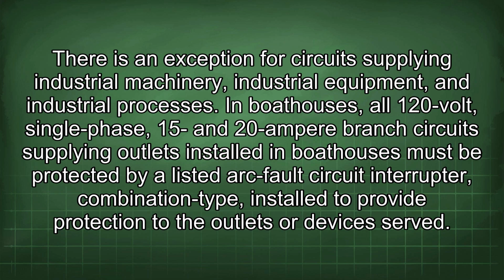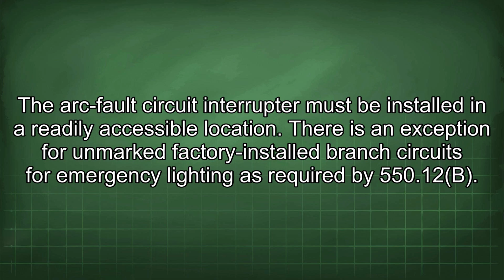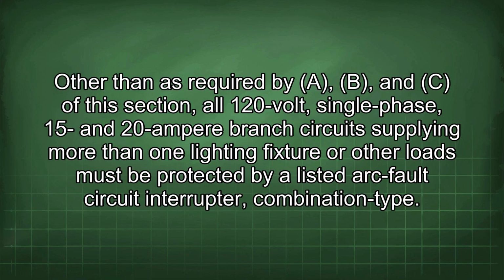In boathouses, all 120-volt, single-phase, 15 and 20 ampere branch circuits supplying outlets installed in boathouses must be protected by a listed arc fault circuit interrupter combination type, installed to provide protection to the outlets or devices served. The arc fault circuit interrupter must be installed in a readily accessible location. There is an exception for unmarked factory-installed branch circuits for emergency lighting as required by 550.12(B), other than as required by A, B, and C of the section.